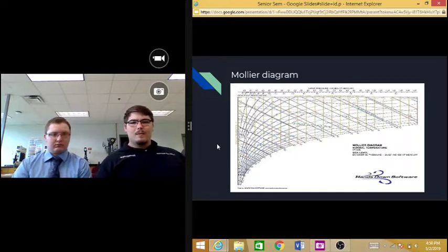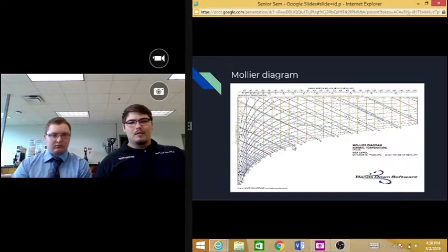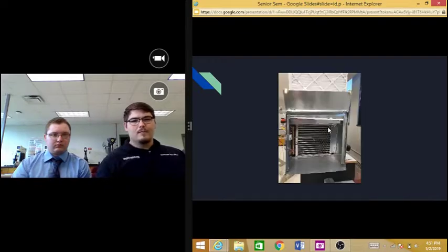This is a Mollier diagram. This is similar to a psychrometric chart. It's just kind of sideways, but this is an industrial standard way of describing how the temperature and the relative humidity are correlated. And effectively, we could drop the humidity through cooling the air down this curve, and then you'd reheat the air back up into a point where it's within the ideal temperature diffusing point, where people are more comfortable with having that air diffuse down their back or over their head through the ceiling tiles.